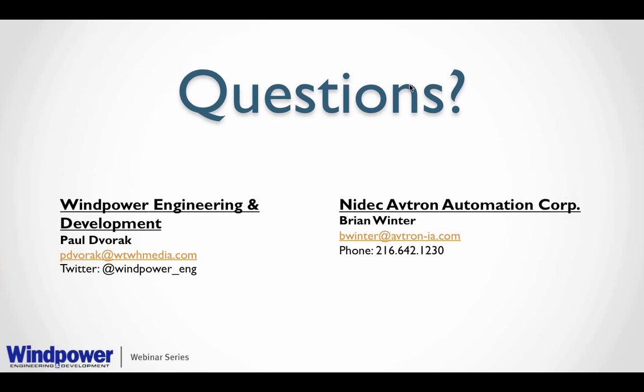That's a good question. GE is probably the right people. You should be reading the GE diagnostic manual for the full procedure on this. I have some familiarity with the GE blade pitch system, however, and so I understand what the goal is: when you plug and unplug, you're trying to verify whether or not you're achieving correct encoder connections. Again, on those systems, I think the GE procedure is correct. They're leading you through the basics.